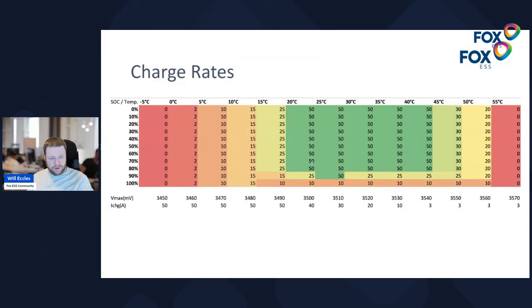Now the amps is important, because if you've got a large battery stack, you will not be using 50 amps to charge them. My battery stack is 440 volts, and I'm charging, I think, at something like 15 or 17 amps at full speed, and that's because my voltage enables the capabilities of the battery to be far greater than that of my inverter. So I'm really only limited by the inverter.